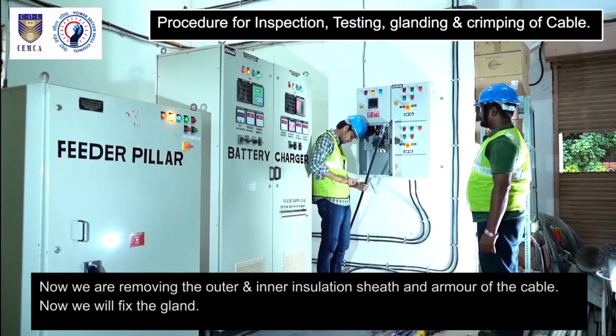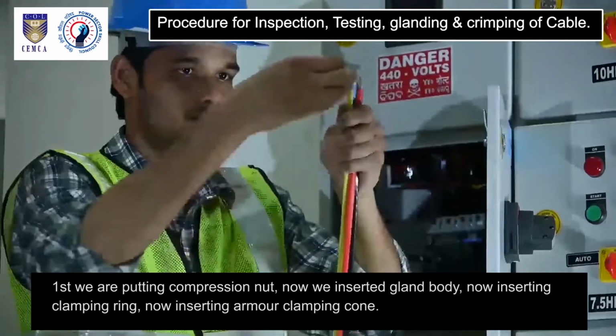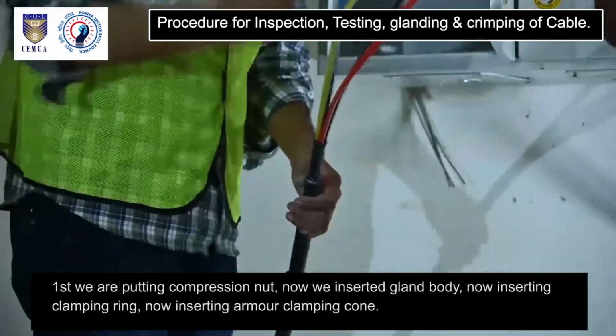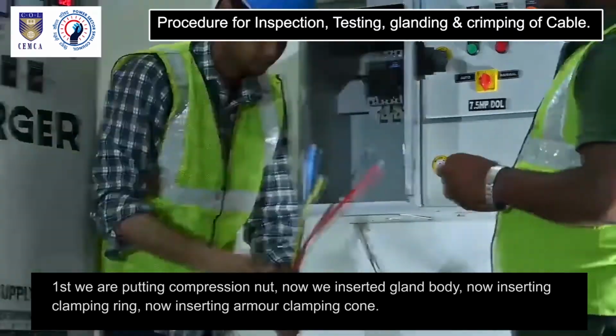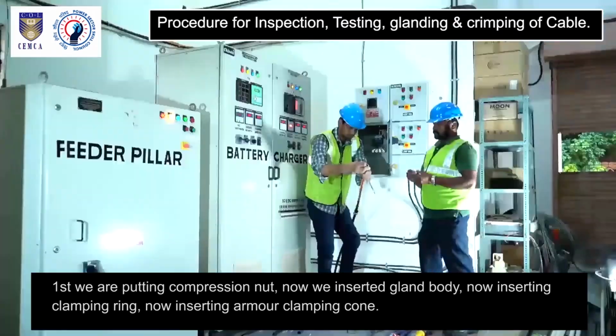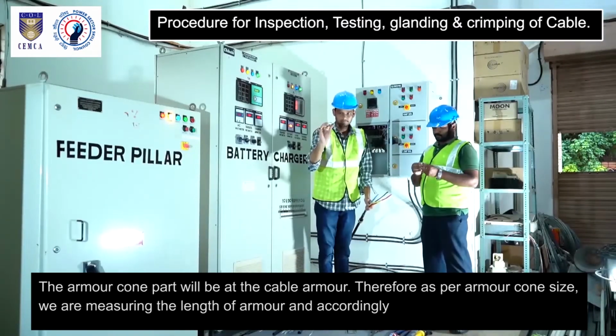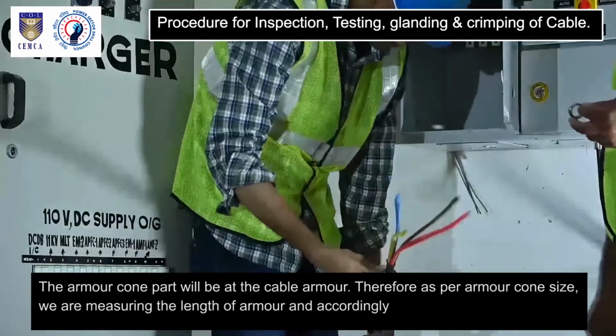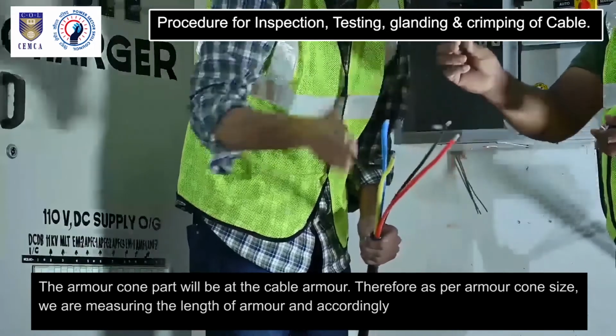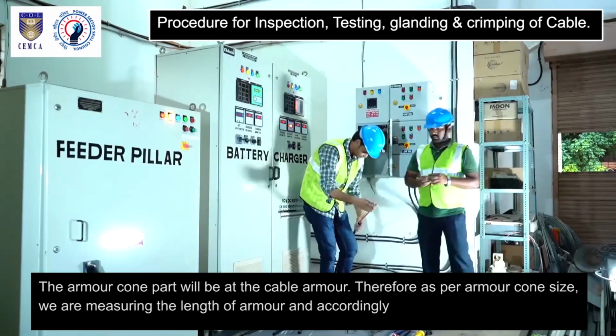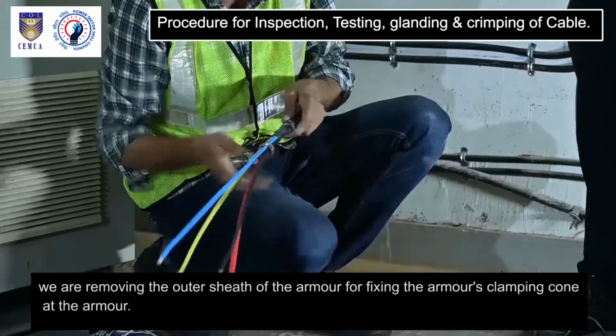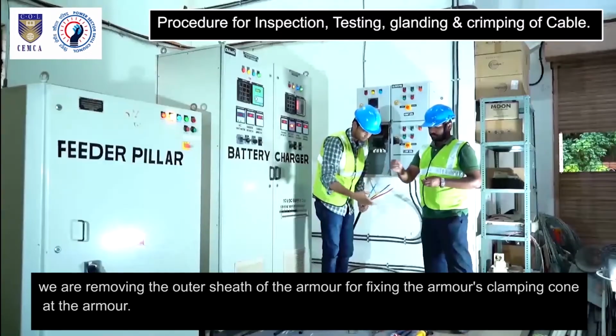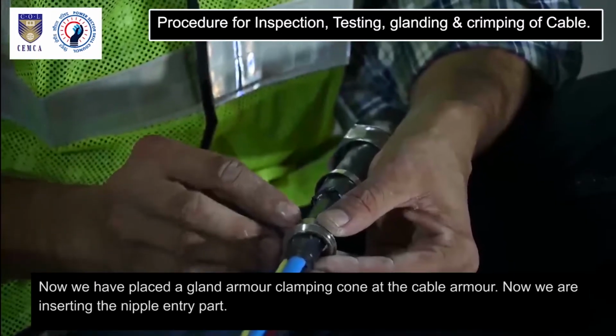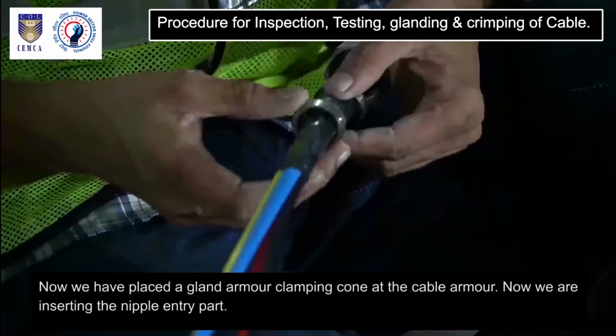Now we will fix the gland. First we are putting compression nut. Now we inserted gland body. Now inserting clamping ring. Now inserting armor clamping cone. The armor cone part will be at the cable armor. Therefore, as per armor cone size, we are measuring the length of armor and accordingly, we are removing the outer sheath of the armor for fixing the armor's clamping cone at the armor. Now we have placed a gland armor clamping cone at the cable armor.